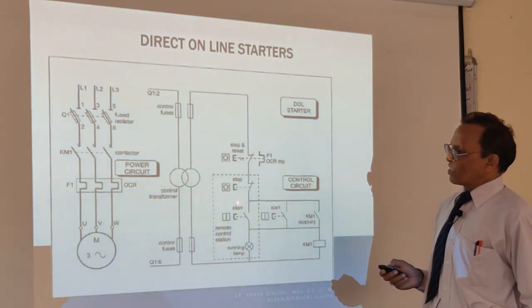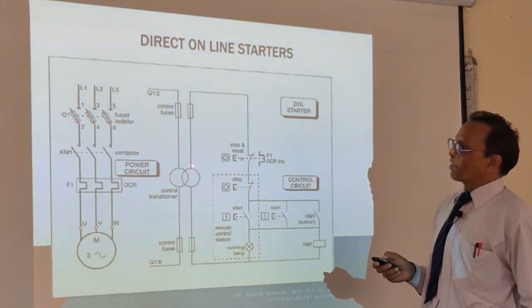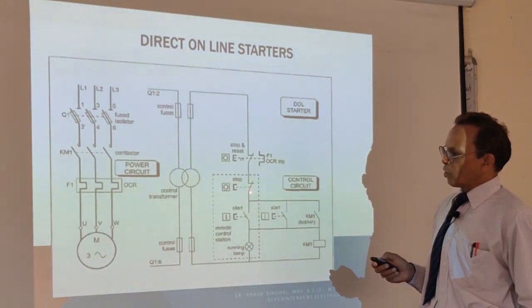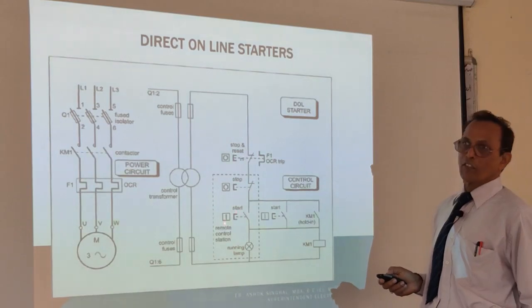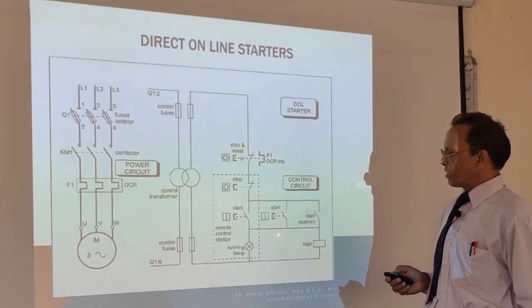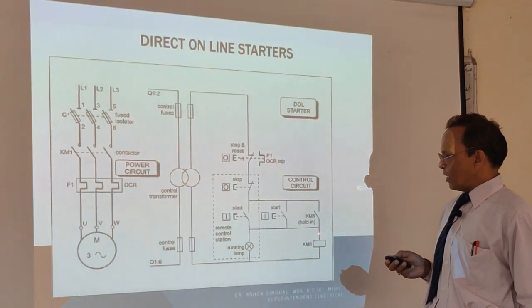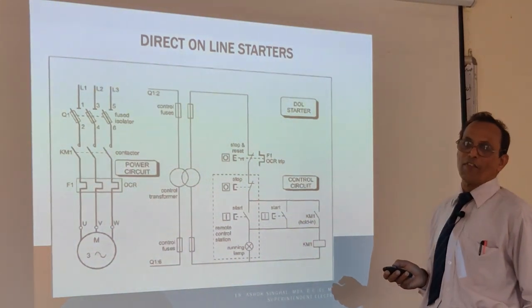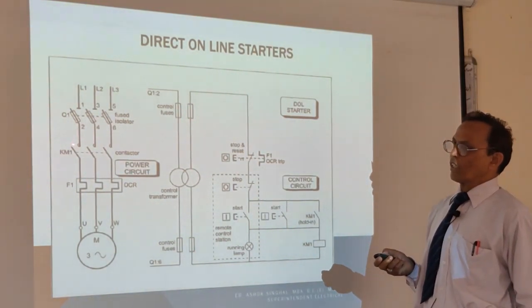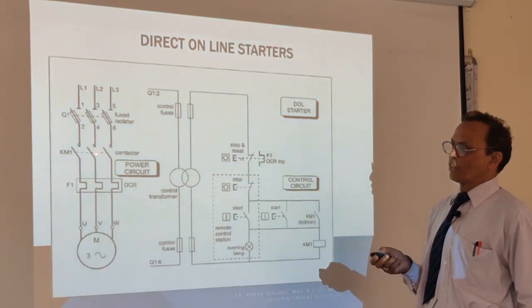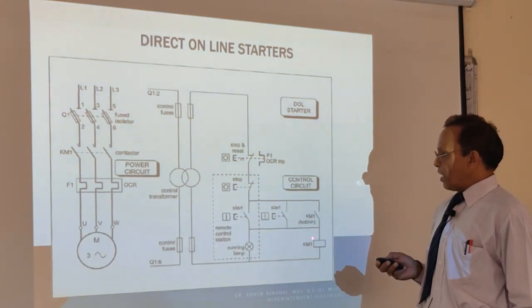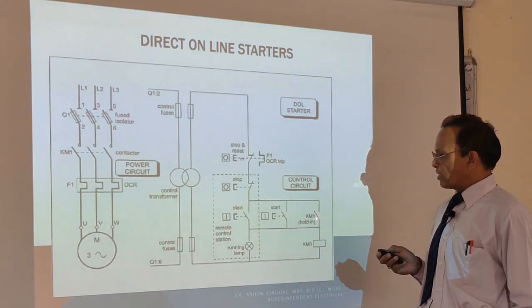When you press the start button, power comes from here through the stop reset button, through the stop button, and through this — the lamp gets on, showing motor indication. Then power comes through the KM1 coil and KM1 gets energized. So KM1 energizes, the contactor is pulled in, and your 440 volt contacts are made. Your motor starts rotating.